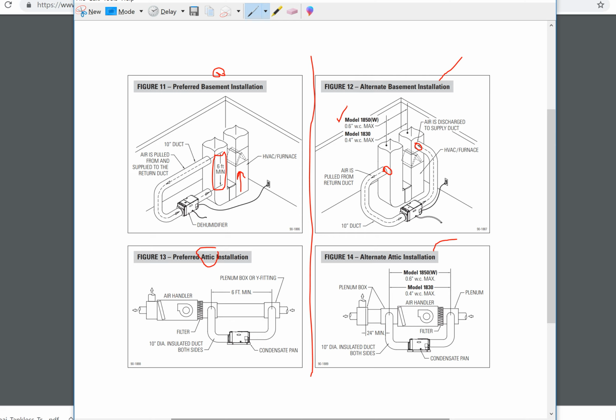Otherwise, if the fan from the system runs at too high of a pressure, it'll actually become a conflict with and block the airflow from the dehumidifier. So the fans are actually pushing against each other in a return to supply configuration, which is harder on each of the blowers for both the air handler and the dehum. Also, the air being discharged into the supply is warmer than the return. So you're taking cold supply air, now you're mixing warm air with it, which could have an impact, minor, but could have an impact on the cooling effect of the air going into the space.